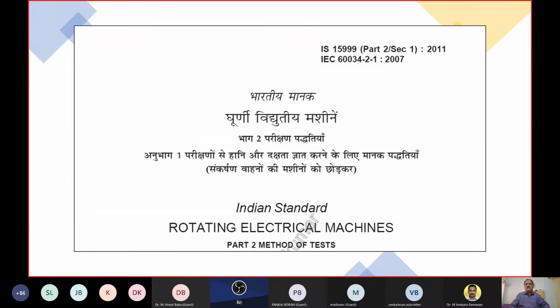IS 15999-2-1 is the equivalent of IEC 60034-2-1, which was originally written in 2007. I mentioned it to you earlier. When a common standard was required throughout the world, IEC revised their standard as IEC 60034-2-1 in 2007. India, along with IS 12615 in 2011, also adopted a testing method similar to IEC and named it IS 15999-2-1 in 2011.